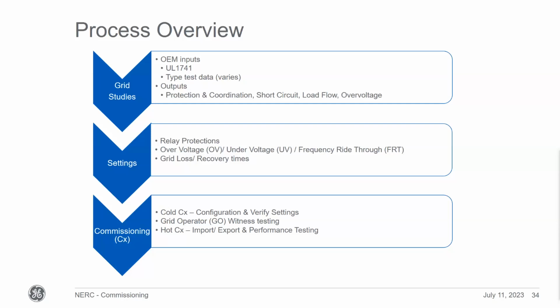Breaking commissioning down pretty simply, there's the cold commissioning stage where we would do the configuration of the inverter, anything that wasn't done in the factory. Depending on what inverter we use, some of them come pre-configured for UL 1741, and it's as quick as setting the inverter to UL 1741, and it'll give us the standard settings. Sometimes there are special settings. We have grid operators that have special settings they would like to see as far as trip times and ride through times.